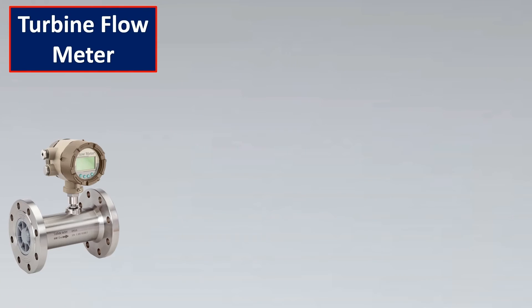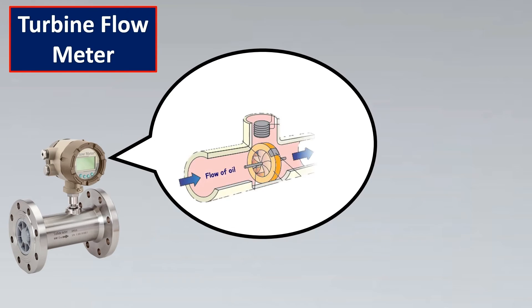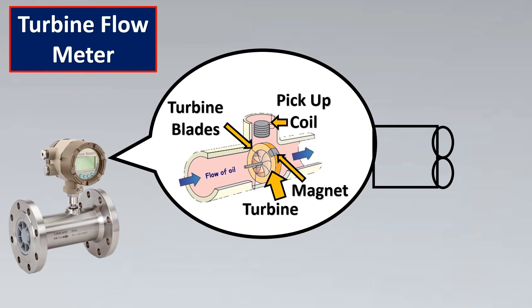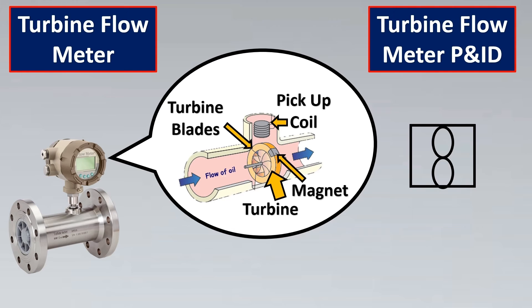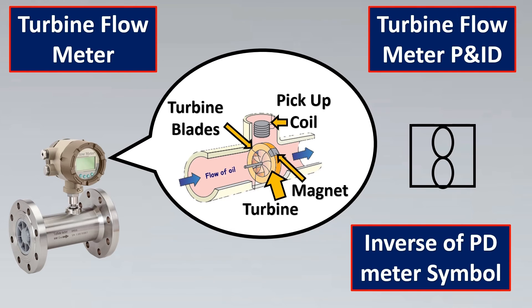The turbine flow meter symbol is very similar to the positive displacement symbol. In a turbine flow meter, flow causes the turbine blades to move; the faster the blades rotate, the higher the flow, detected by a magnetic pickup coil. The most important elements are the blades, which are shown in the symbol along with the body. Notably, this is the inverse of the positive displacement symbol — where the vanes are shown in the horizontal plane, the turbine blades are shown in the vertical plane.